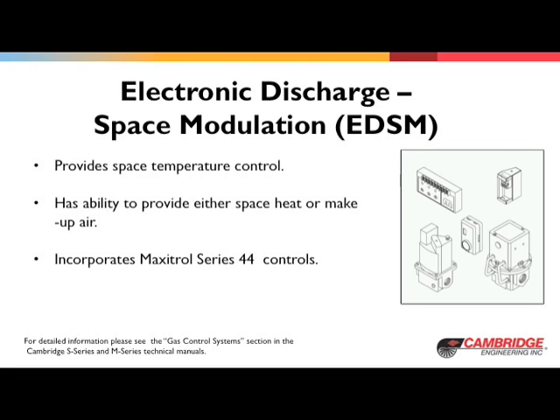A 3 degree drift from the STS setting will cause the heater to modulate the discharge temperature of the heater to the actual setting of the min and max fire pots on the amplifier. If the space temperature is close to the STS setting, the heater will discharge somewhere between the min and max pot settings.